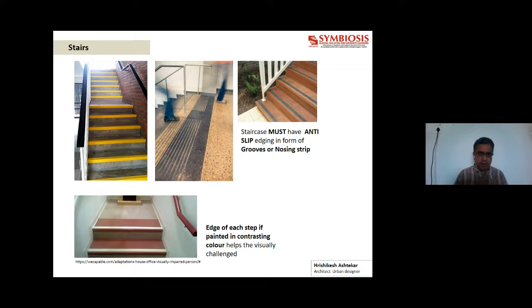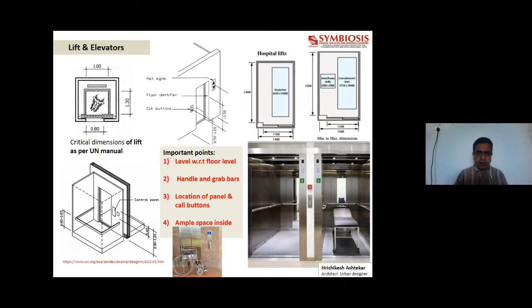Next. Then we come to the next part, which is the elevators. If you look at it, it is very clear what the key things are. First is the level with respect to floor level. It should stop exactly at the floor level. Then it should have handles and grab bars, which it has, if you look at the photos of the elevator, on all sides. The third is that the location of the panel and call buttons should be at low level so they can be pressed easily. And there should be ample space inside. This hospital stretcher lift, which is generally provided, has all these things, so one does not have to worry. But if it is a normal elevator, one has to check all these things. Next.